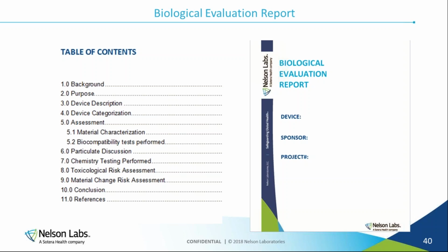Not that everyone's going to have one, but it's so common from when you get this device and your engineers say, we're done, this is it, we love it, and you submit it for testing and you spend a lot of time and money on this testing, and then they come back and say, we're going to use this material because our supplier backed out or something like that. So we can assess that change right in your biological evaluation report where you're not starting from scratch and everything is contained in one document.